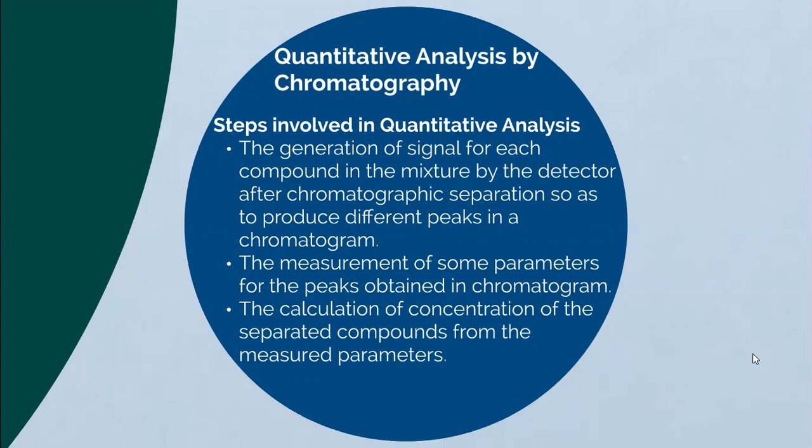The specificity of the detector may cause certain peaks to be missed in the quantification process. Similarly, the flow rate of the mobile phase and the temperature of the column and detector determine the accuracy of quantification. For example, a differential refractive index detector requires good control on temperature, while an ultraviolet detector is less critical in this respect.